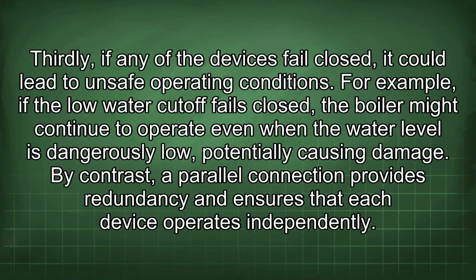Thirdly, if any of the devices fail closed, it could lead to unsafe operating conditions. For example, if the low water cutoff fails closed, the boiler might continue to operate even when the water level is dangerously low, potentially causing damage.